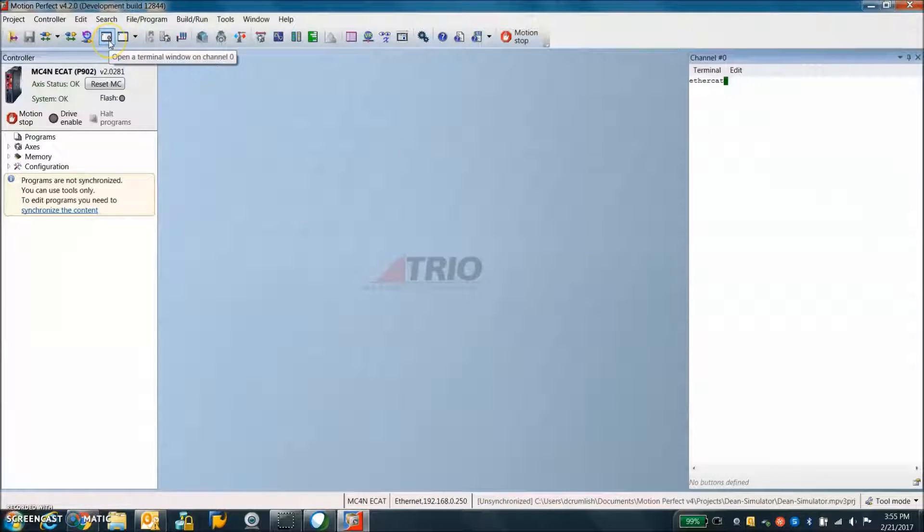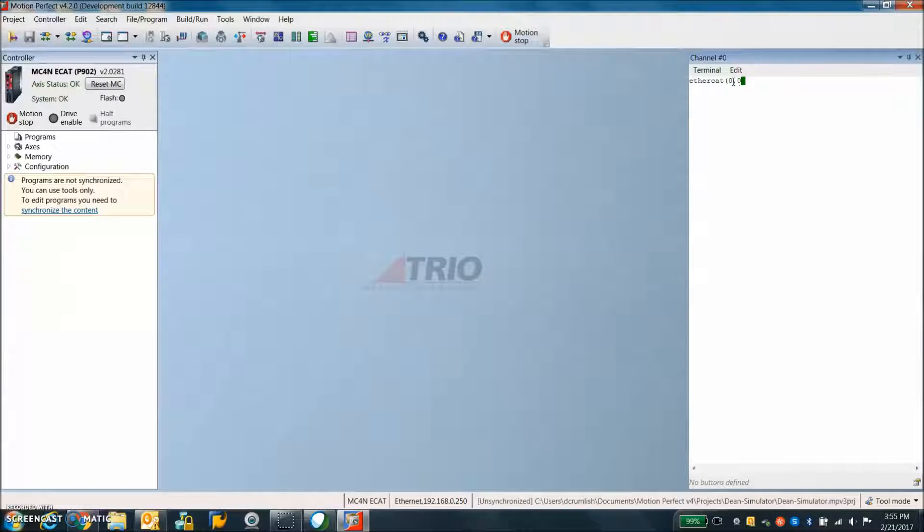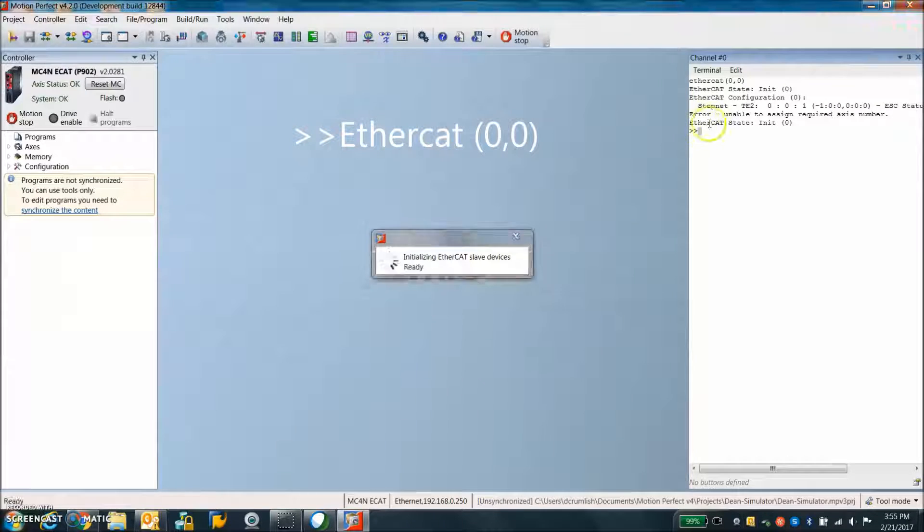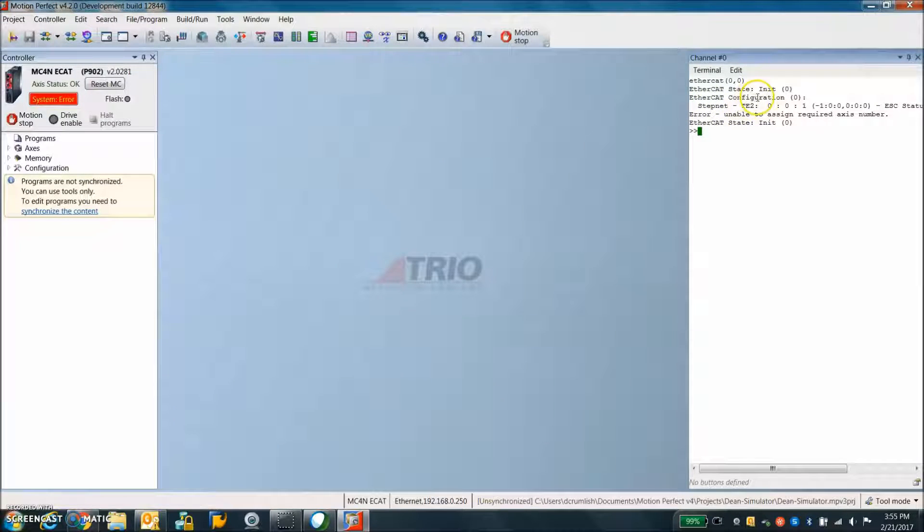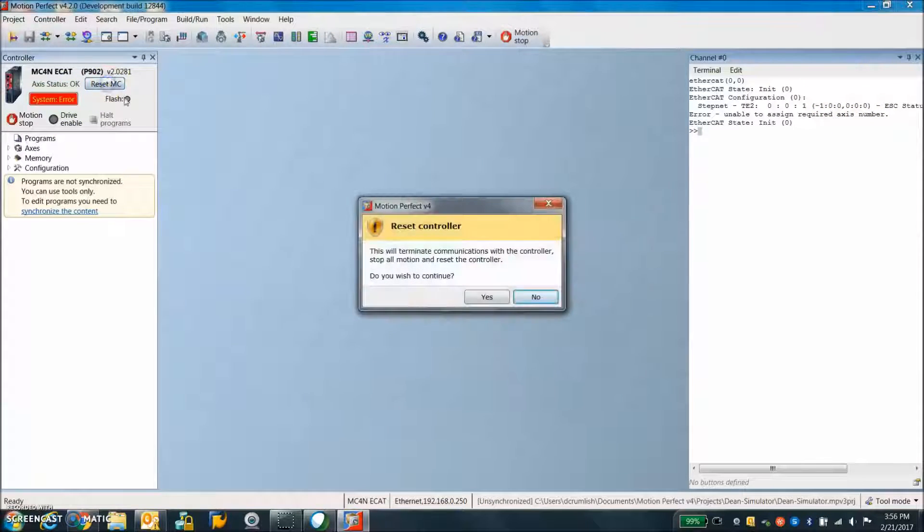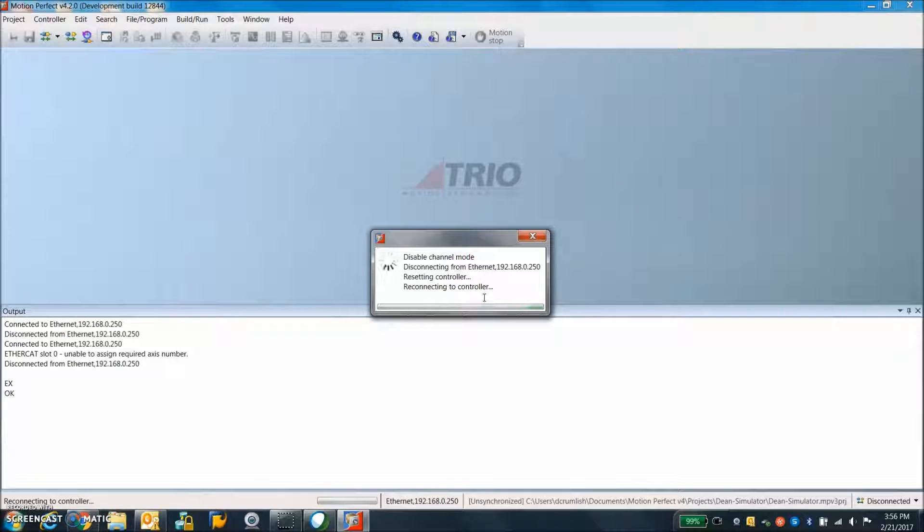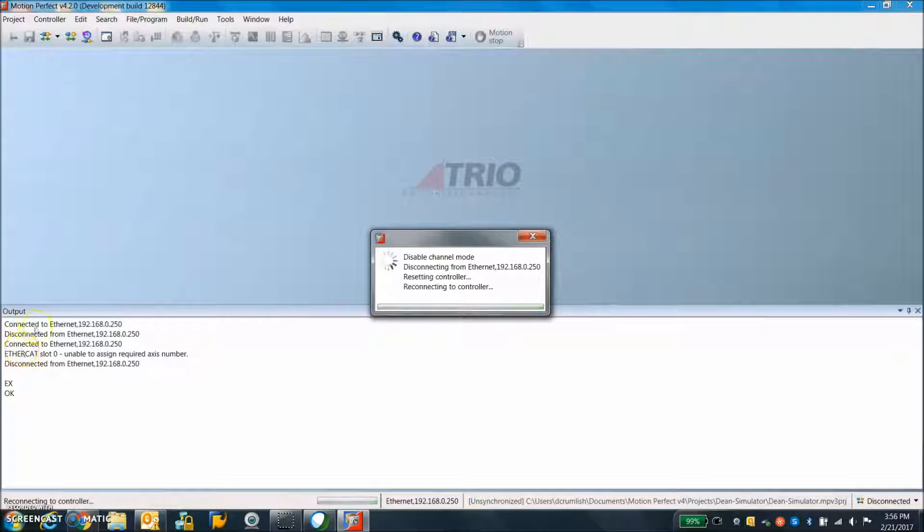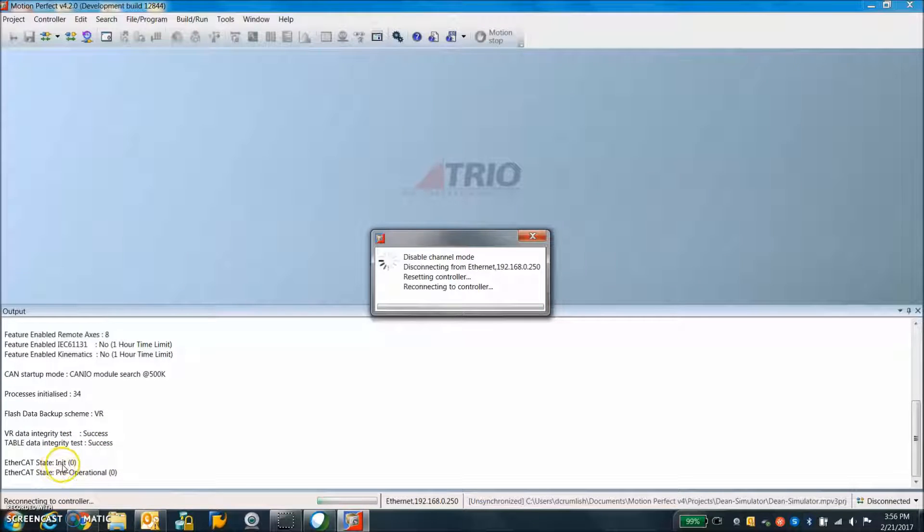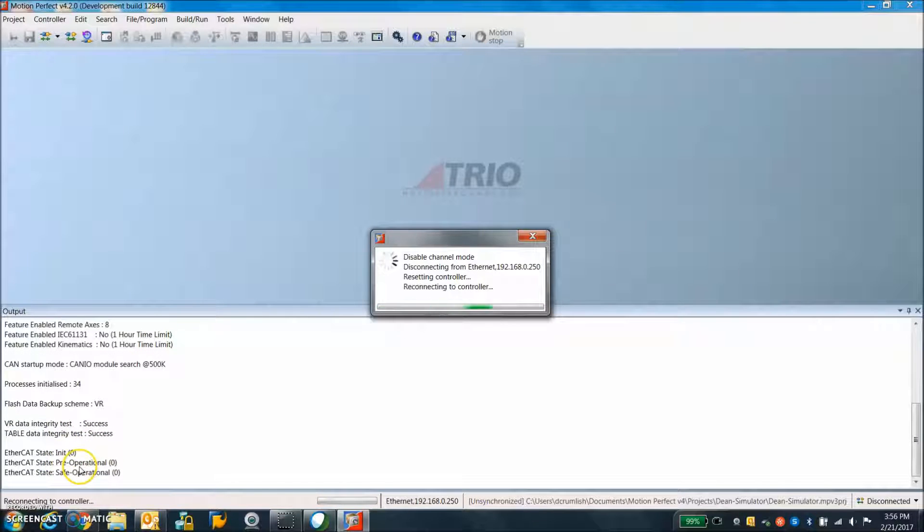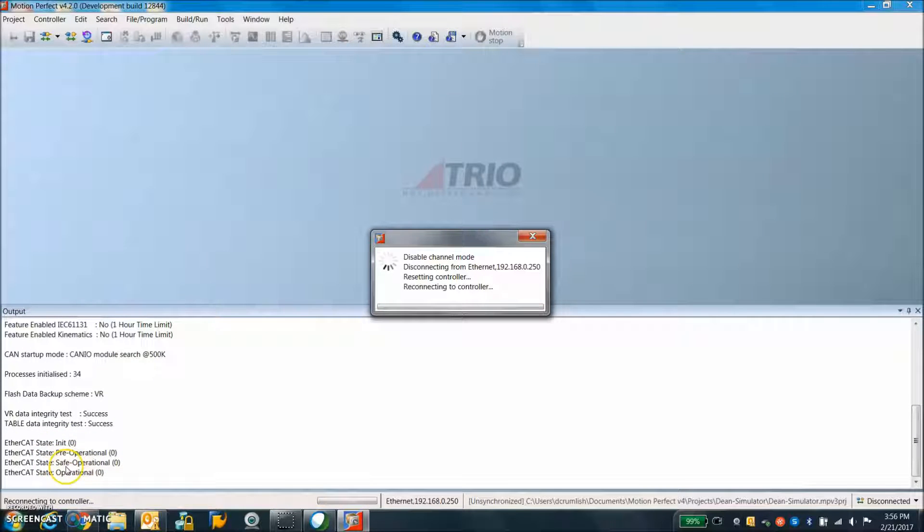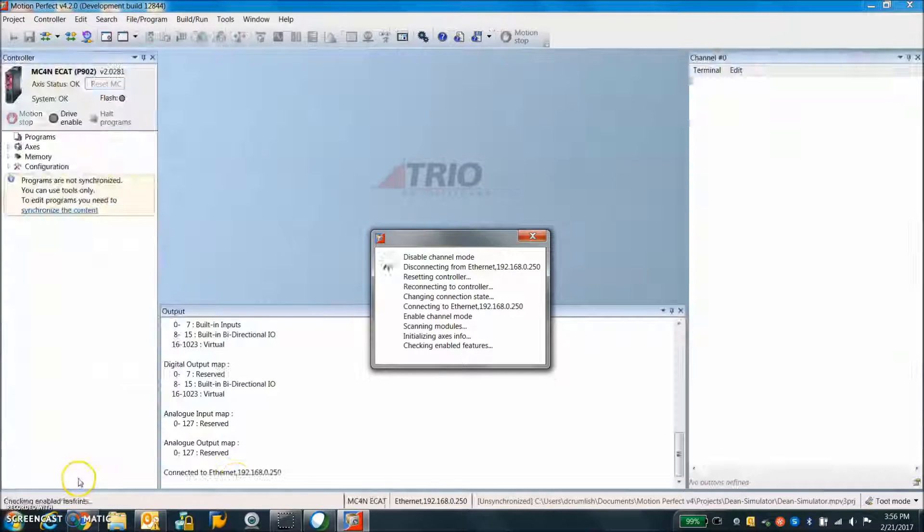So I'm going to open up a terminal zero and click on it and enter the EtherCAT initialization message which if we're connected should do something. Okay there's a little bit of a problem here. I'm going to try resetting the motion controller and drives are configured properly and we'll see how this comes up. We can see on the output screen there's the EtherCAT auto initialization. We're in init, then pre-operational, safe-operational and then operational state. That's the state we want to be in after power up or reset.